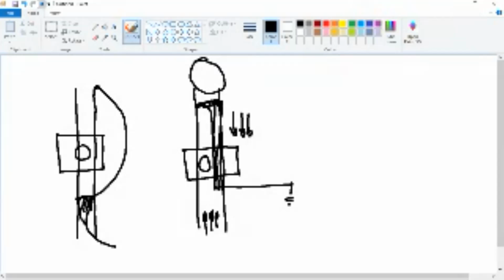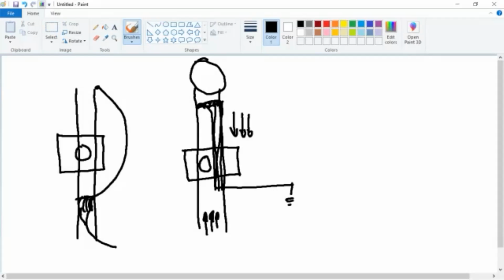Why? It's got to do with this direction. Why would the fault indicator still work? Anybody? Am I still online? Yeah. Okay. Any guesses? Fault to ground. Right, the fault to ground is going to occur, but what's happening with my neutral that's going up the conductor and back out of the conductor?